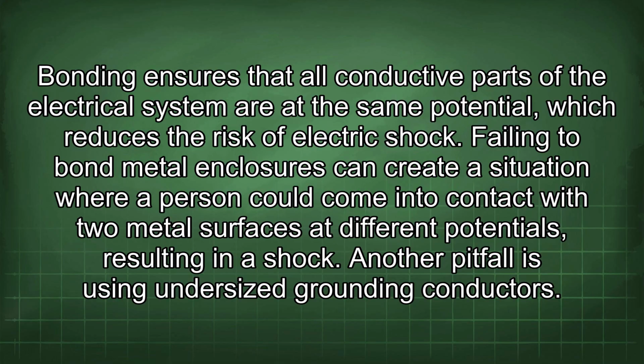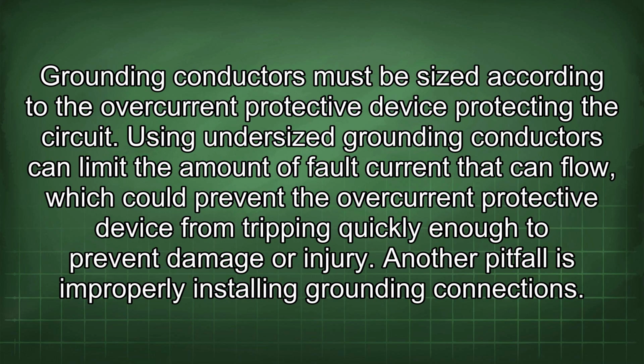Another pitfall is using undersized grounding conductors. Grounding conductors must be sized according to the overcurrent protective device protecting the circuit. Using undersized grounding conductors can limit the amount of fault current that can flow, which could prevent the overcurrent protective device from tripping quickly enough to prevent damage or injury.